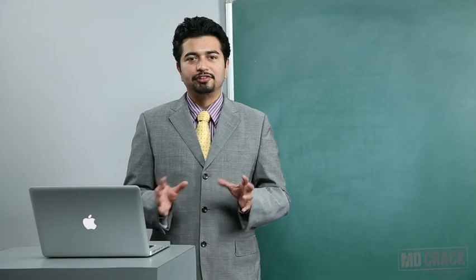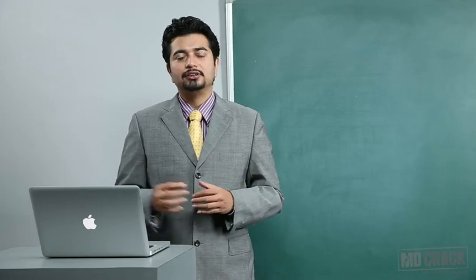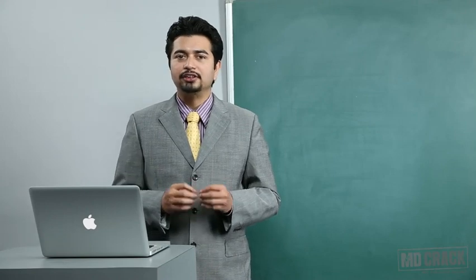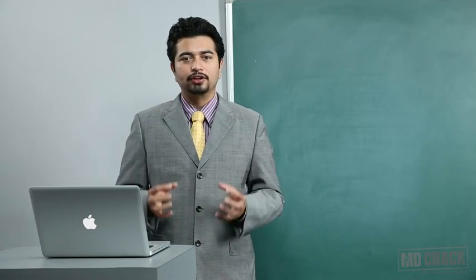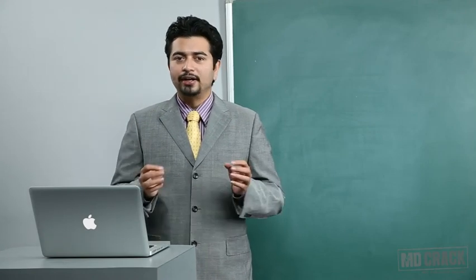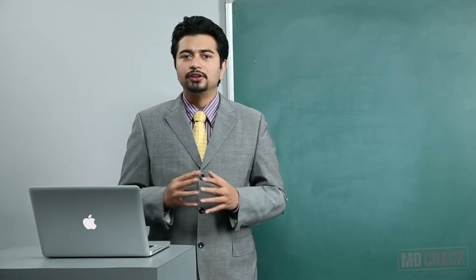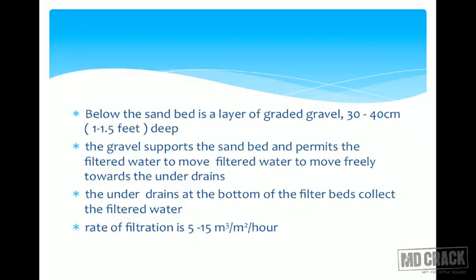One notable difference is the size of the sand. The size of the sand in the rapid sand filter is larger so that water flows more freely, whereas in the slow sand filter it was much smaller and therefore water flowed much more slowly. The rate of filtration in the rapid sand filter is very fast — 5 to 15 cubic meters per square meter per hour — much faster than the slow sand filter.